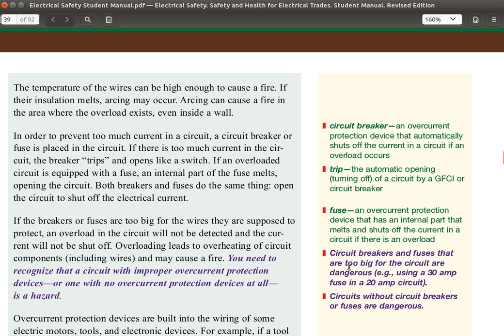Circuit breakers and fuses that are too big for the circuit are dangerous. Example, using a 30 amp fuse in a 20 amp circuit. In that case, the 30 amp fuse would see 25 amps as just normal current, thinking that it's a big machine being operated. However, it's a fault current, and it did not trip because the circuit breaker is too large. Circuits without circuit breakers or fuses are dangerous. Circuit breakers and fuses are really protection devices, and you need the protection there. If these breakers or fuses are too big for the wires they are supposed to protect, an overload in the circuit will not be detected and the current will not be shut off.